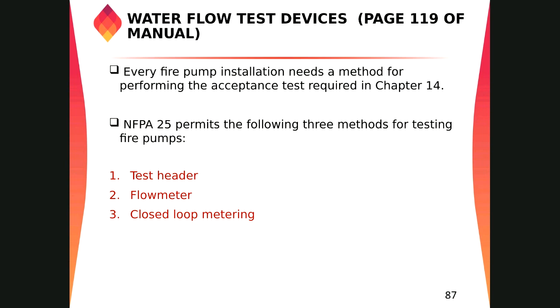So for every fire pump installation, when you put your fire protection system into service, you have to do the pump acceptance test, which is required to be witnessed by the contractor, the client, the fire protection consultant who approved the drawing, and one person from the pump manufacturing company.